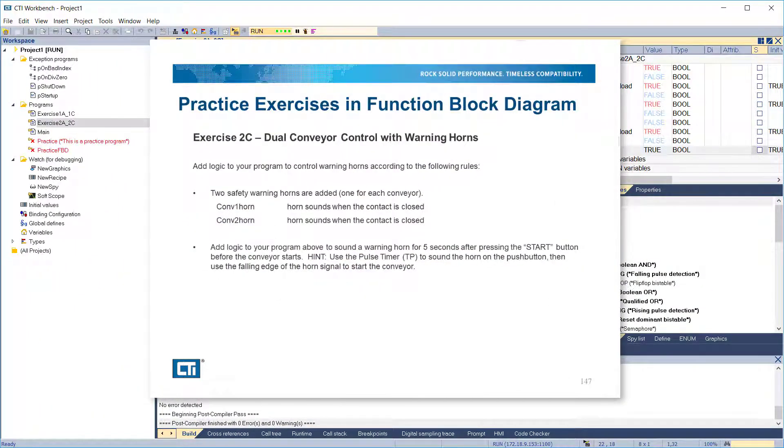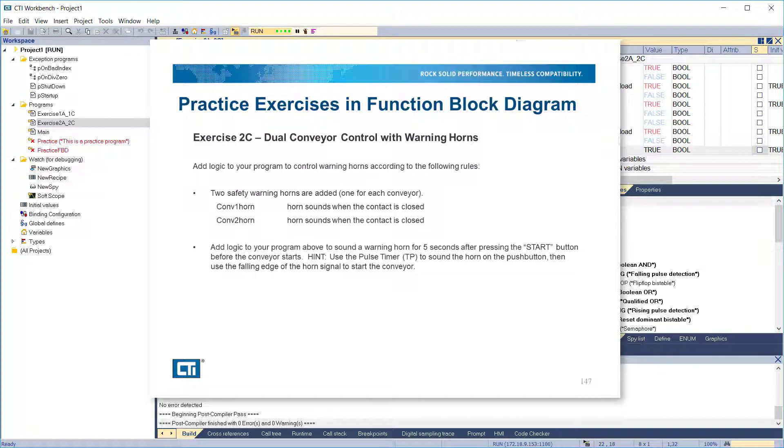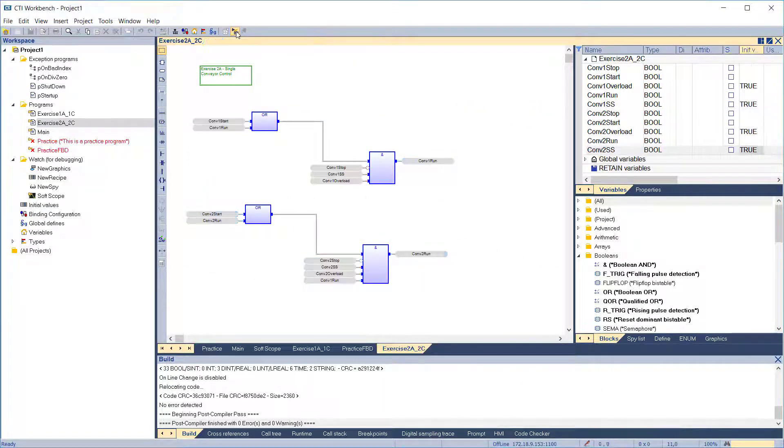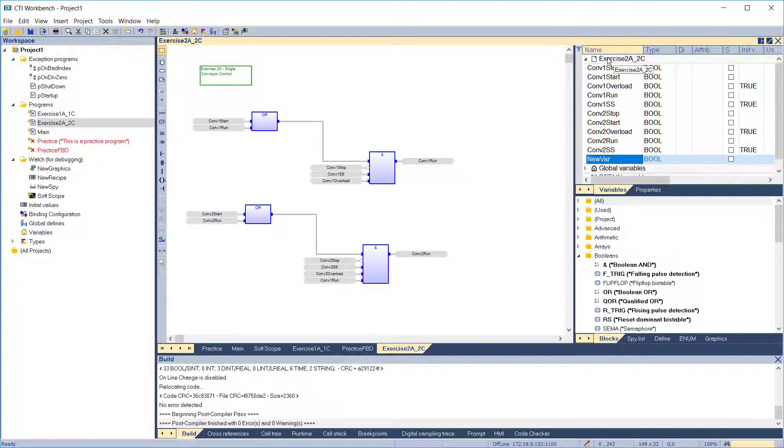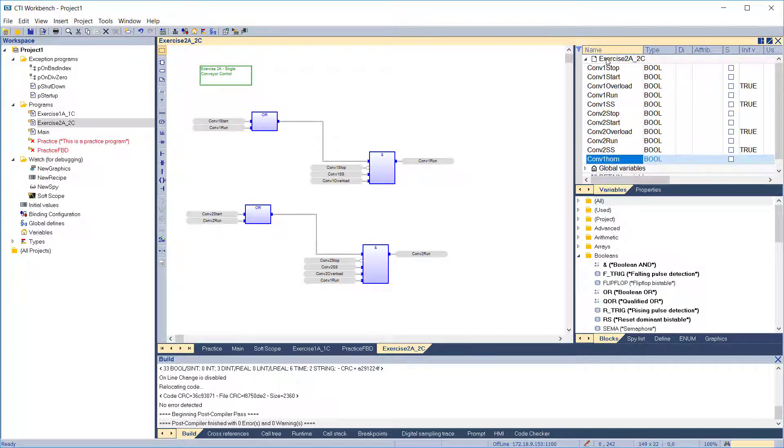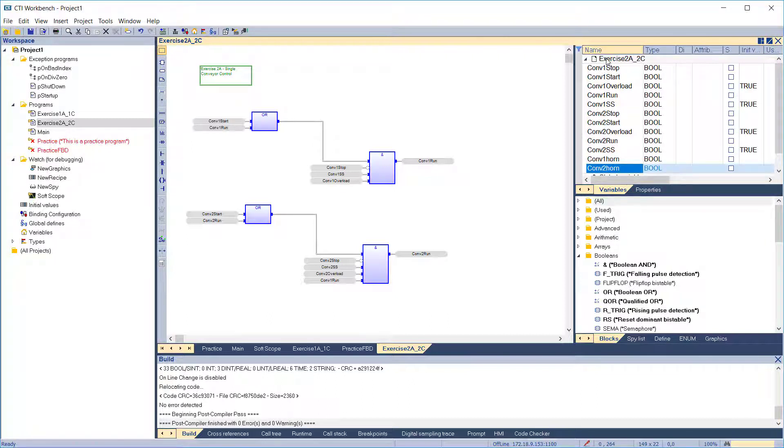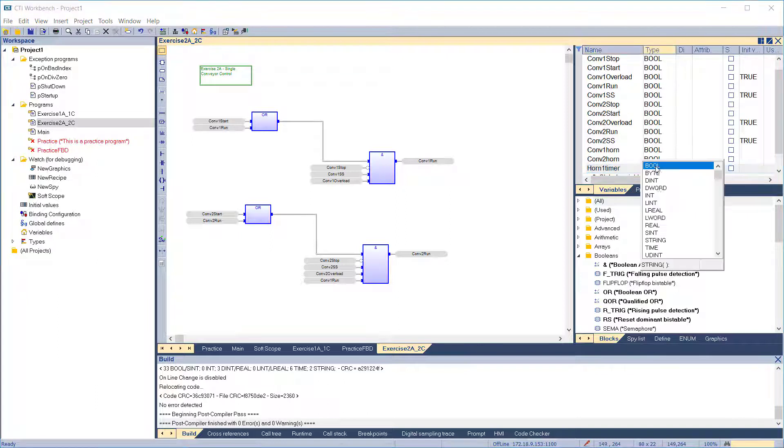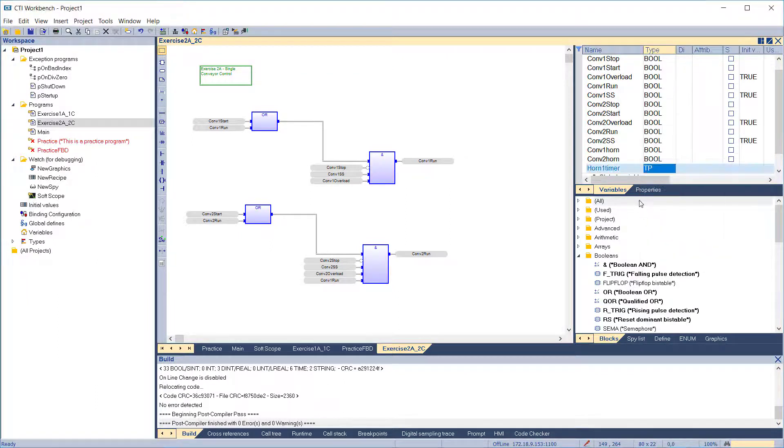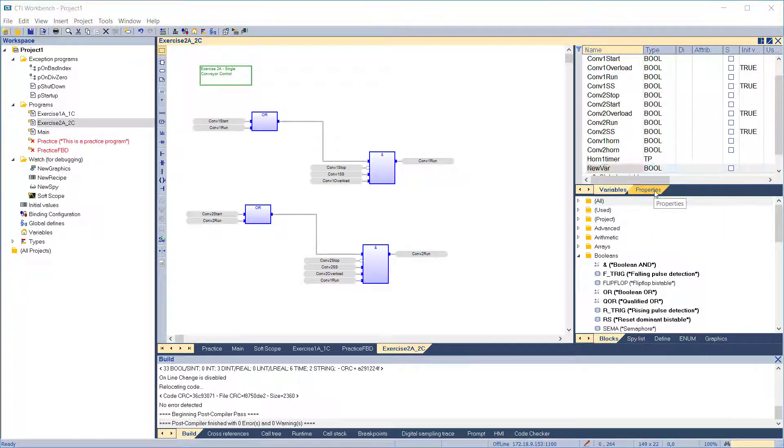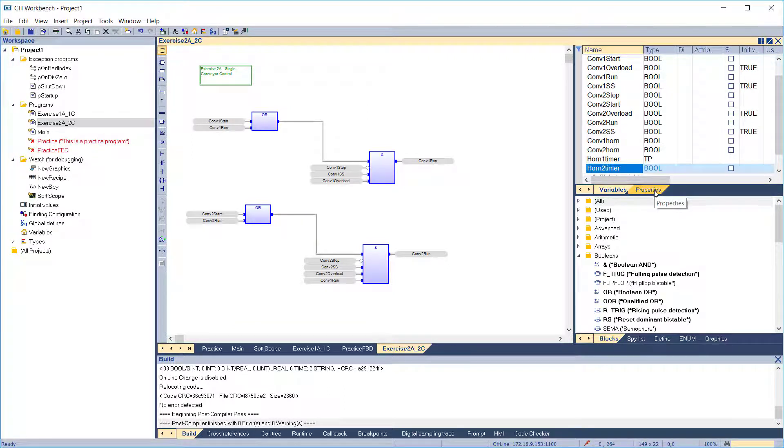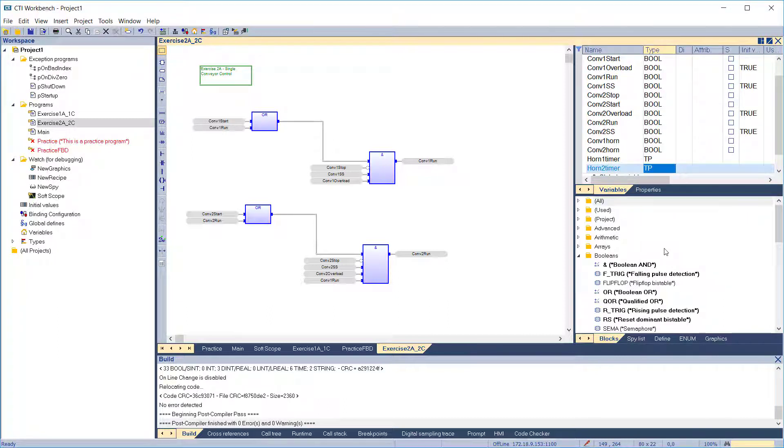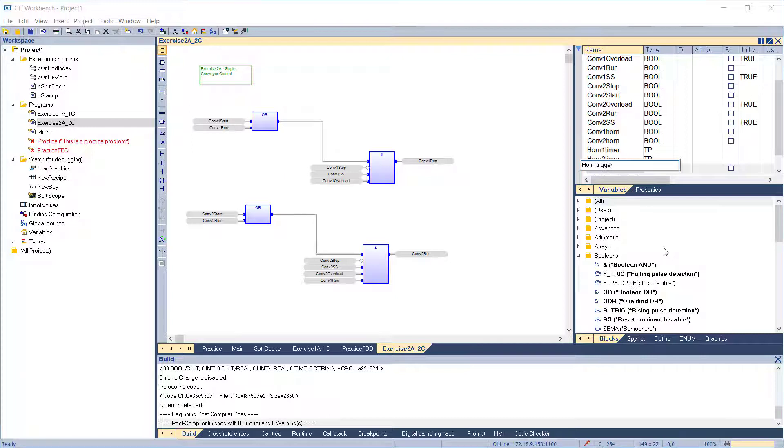In exercise 2C, two safety warning horns are added, one for each conveyor. We'll add logic to our program to sound a warning horn for 5 seconds after pressing the start button before the conveyor starts. We'll use the pulse timer to sound the horn on the push button, then use the falling edge of the horn signal to start the conveyor. We'll create the variables we need: conveyor 1 and conveyor 2 horns, timers for the two horns with type TP pulse timer, and two variables for the falling edge detection function blocks with variable type Ftrig.